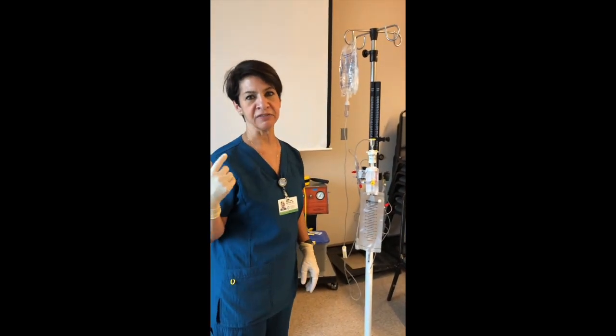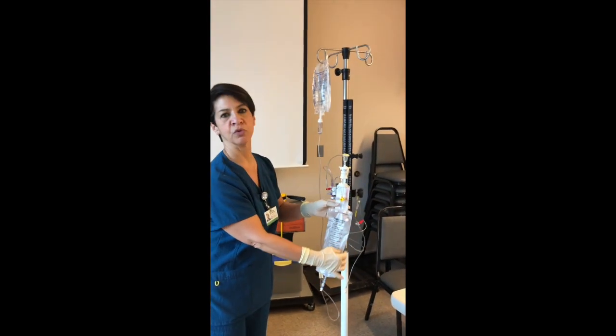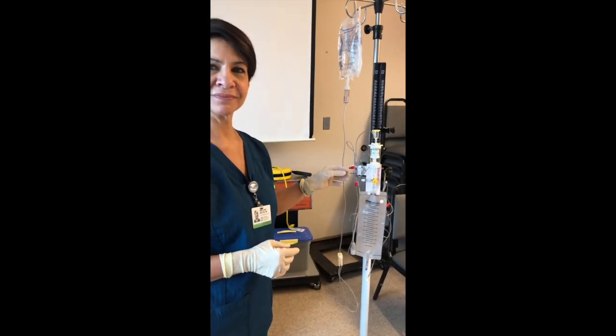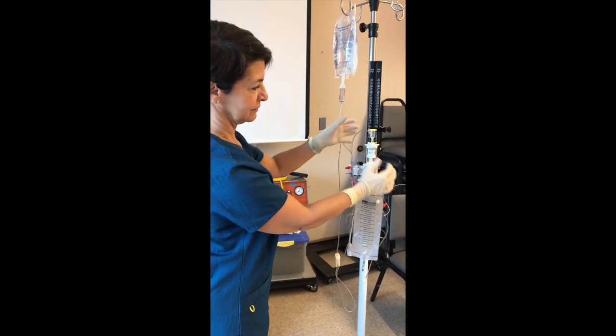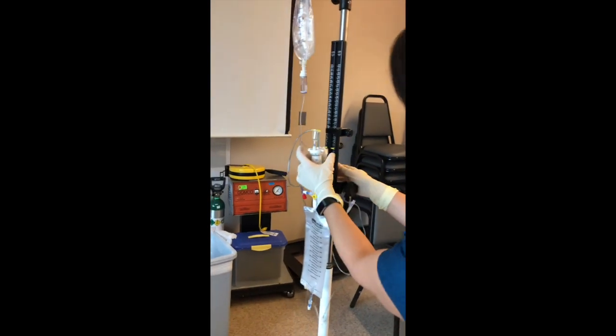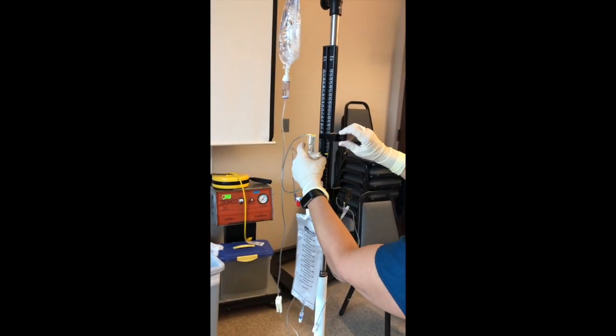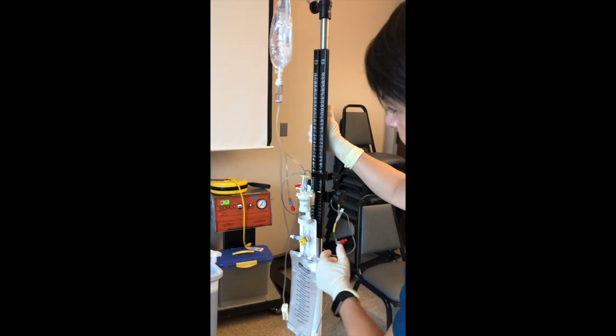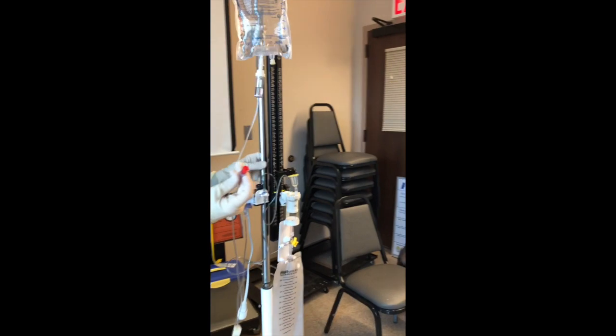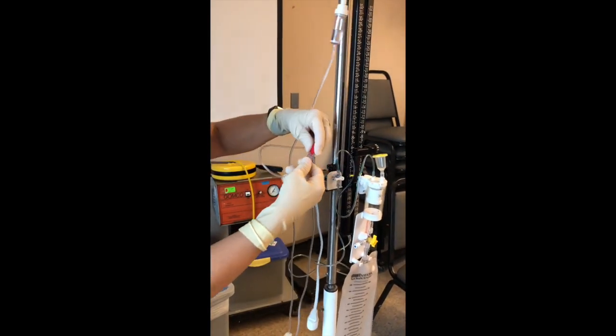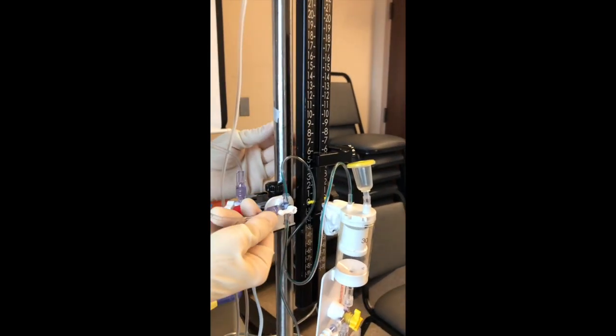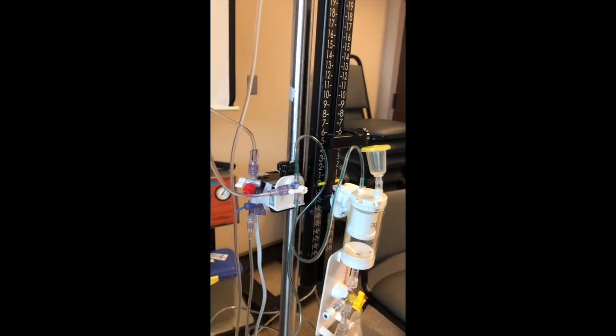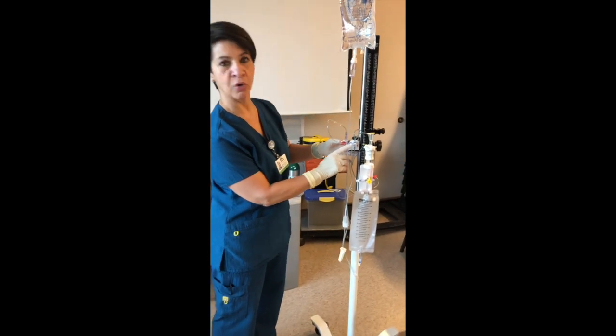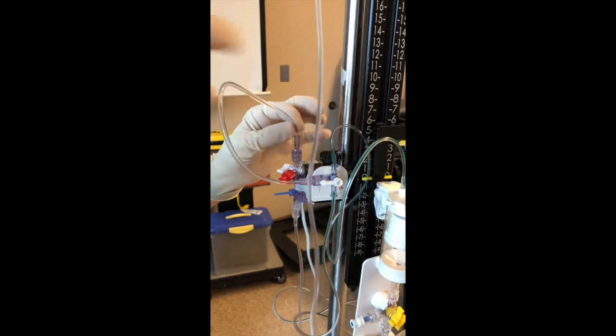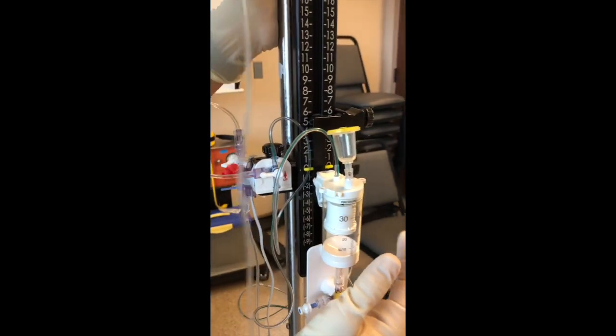While the physicians are inserting the EVD, we're going to be preparing this cylinder for drainage. With clean gloves, attach the EVD graduated cylinder to the vertical reference ruler. There's a hook right here that it would sit on. Attach transducer tubing to intersection port on EVD tubing. So this port here, the short tubing that we originally set up before, is going to go to the air port on this EVD tubing. Always be sure that the air ports are all aligned: the drainage, the flush system, the EVD tubing, and also the pressure line on your drainage bag.